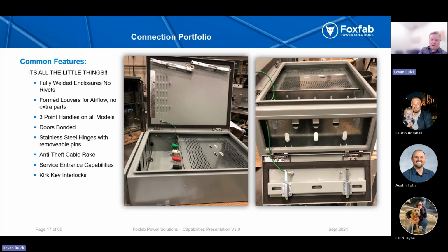All of our outdoor enclosures are fully welded, meaning each edge has a seam all the way down it that's ground smooth and clean. All of the louvers are formed right into the doors instead of a louver plate added afterward. The problem with adding a louver plate after is it creates an area for moisture to get trapped in between. When the louvers are built right into the doors, there's no extra area where corrosion can start.